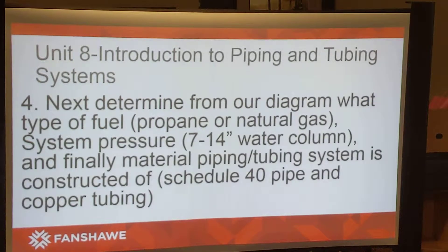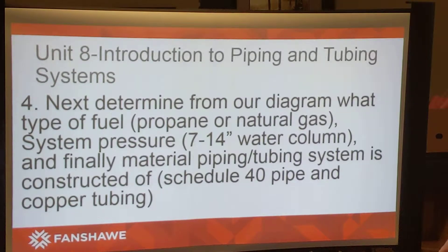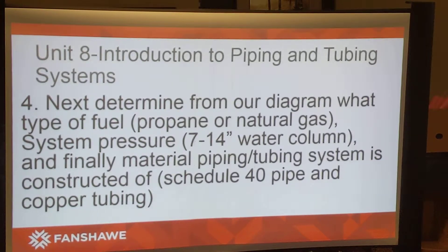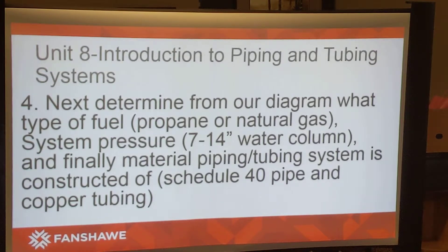Next, from our diagram we're going to determine what type of fuel we're going to be using. We're using natural gas, but it could be propane — in that case we'd use the Annex B tables. In our case we're using natural gas so it's Annex A. The system pressure is seven inches water column, and the material is both schedule 40 pipe and copper tubing.